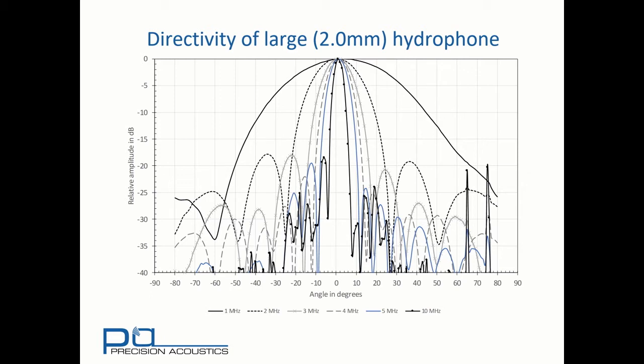Consider here a hydrophone active element that is large relative to the wavelengths it's being used to measure. Here we're looking at signals in the 1 to 10 MHz range. And we can see that even at 1 MHz, the lowest frequency of interest in this chart, there is a 10 dB fall off from normal incidence by the time we achieve plus or minus 40 degrees. Similarly, a signal that's 10 dB below the peak is achieved at 10 MHz by changing the angle of incidence by only plus or minus 3 degrees. A hydrophone of this size would be very sensitive to angular misalignment during experimentation.